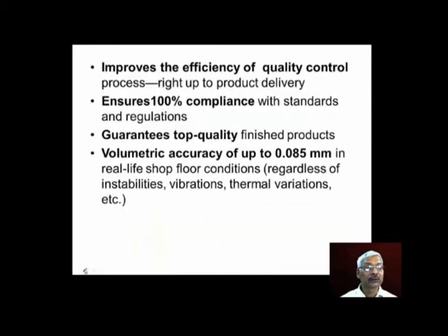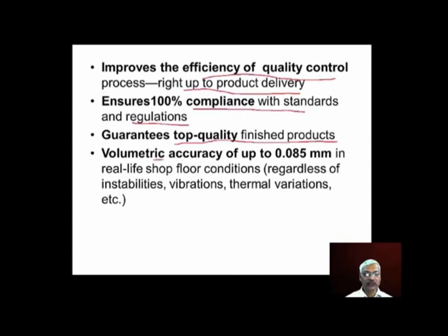Now this portable CMM improves the efficiency of the quality control process right up to product delivery. This ensures 100% compliance with the standards and regulations, and it guarantees top quality finished products and volumetric accuracy of up to 0.085 millimeter in real life shop floor conditions, regardless of instabilities, vibrations, thermal variations, etc.